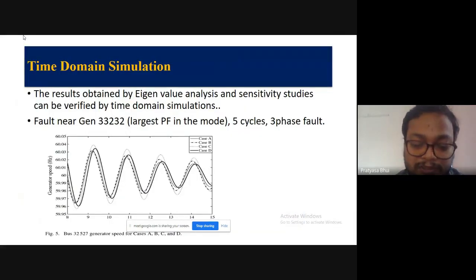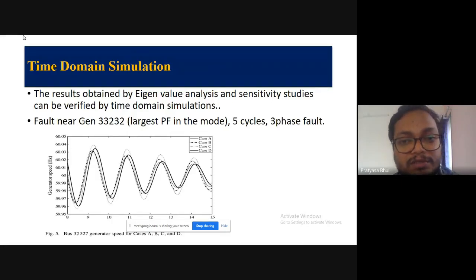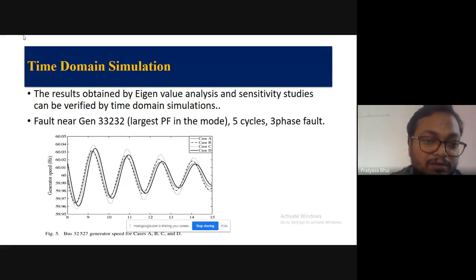The results we got from eigenvalue sensitivity studies can be verified with time domain simulations. You can see that after a fault near generator 33232, which has the largest participation factor in that mode, so basically it has a huge influence on that mode. There was a 3-phase fault near that generator, and you can see the generator speed curve.